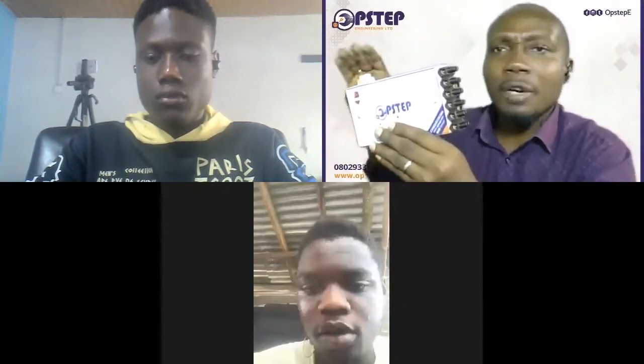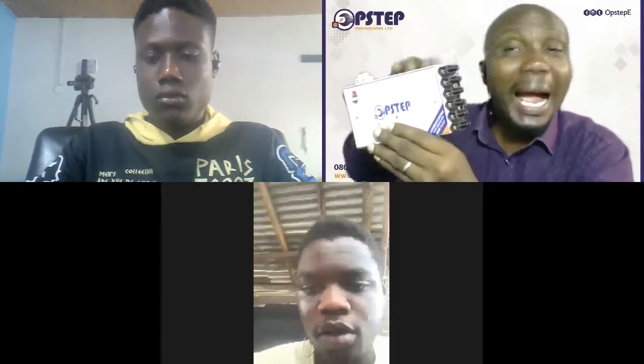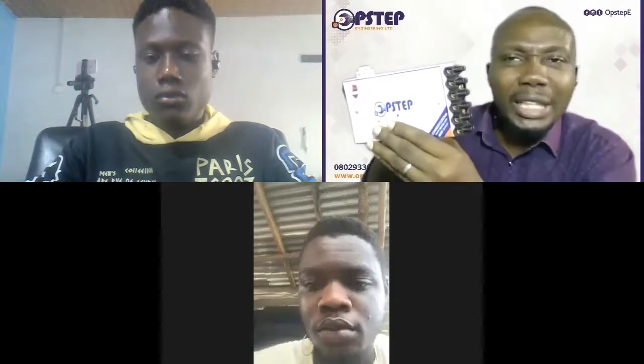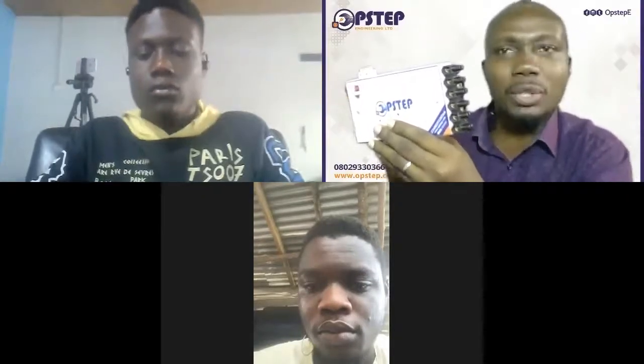Usually when NEPA light comes in, it comes in with some inrush. Sometimes it fluctuates, some other time it is a bit high until load begins to be on it before the voltage stabilizes. That voltage inrush can sometimes damage your electronics if it goes into them directly. So what this box does is help you hold that voltage down for 10 seconds while giving you an audible alert of NEPA's presence. After that 10 seconds, the system automatically switches the house to the NEPA lights. While you're on the NEPA light, it automatically turns off your generator. That is what this box does.